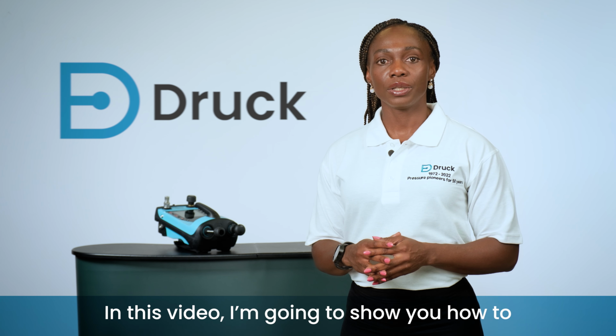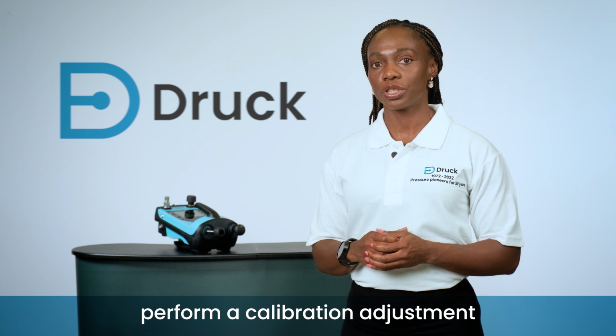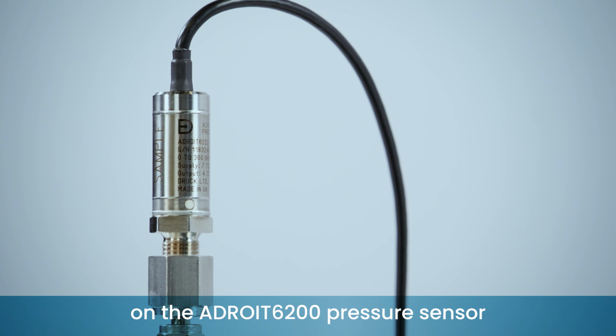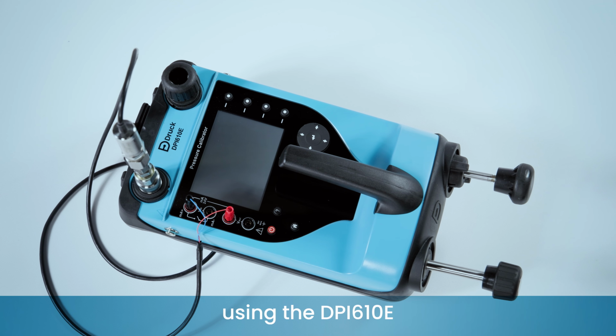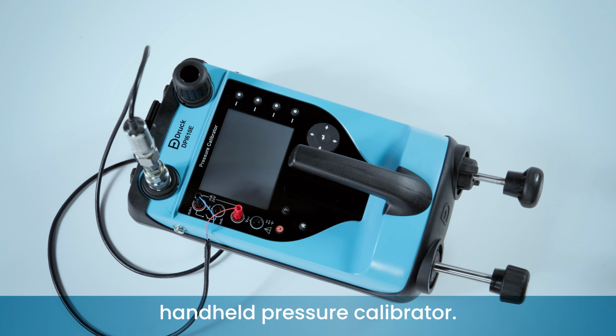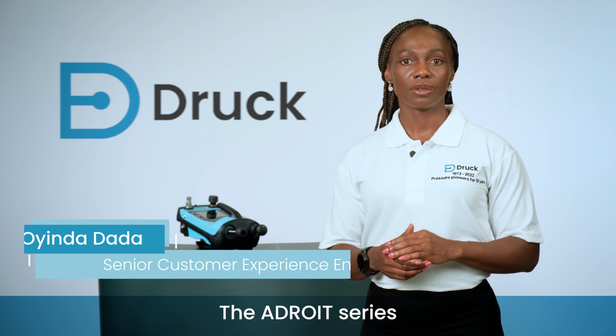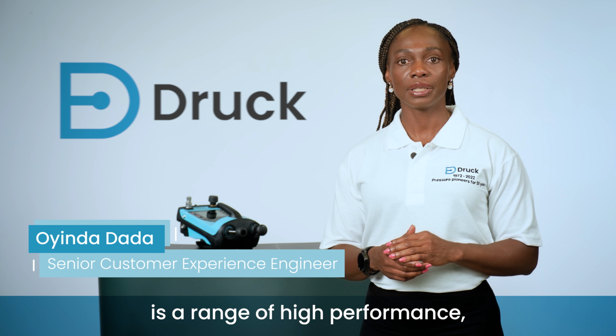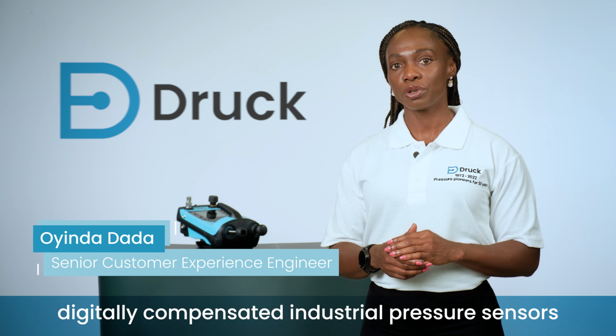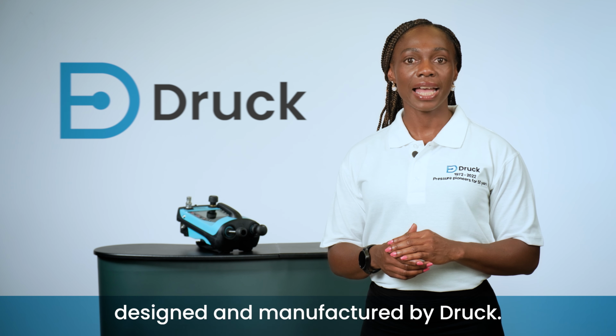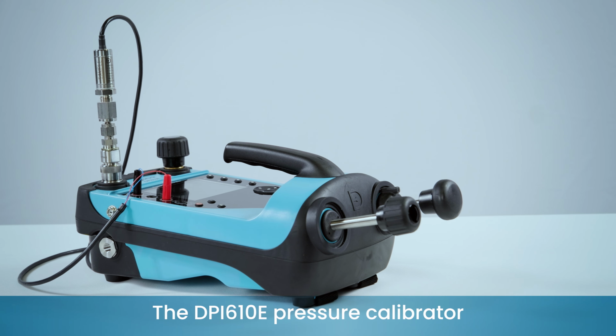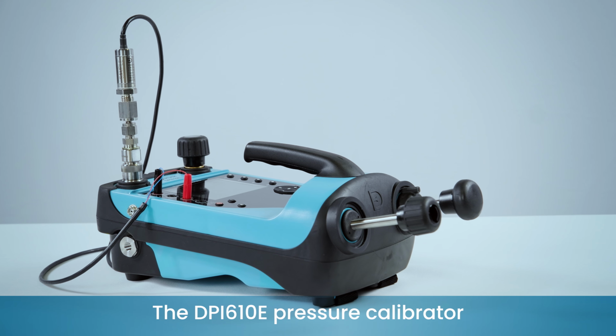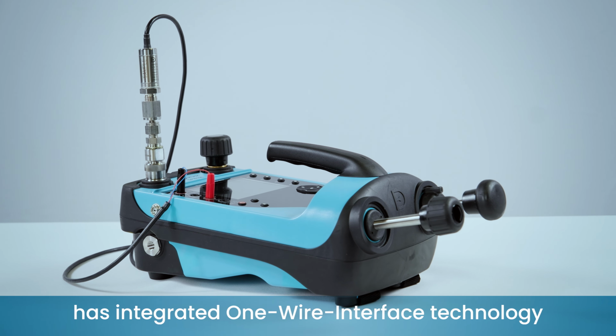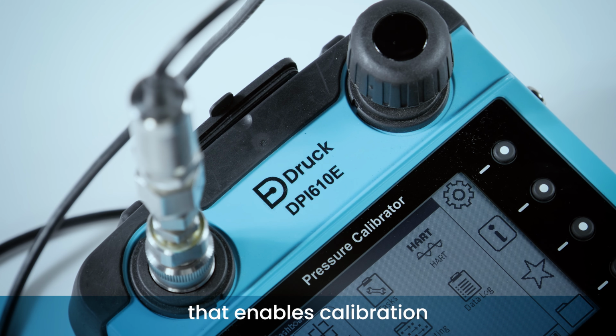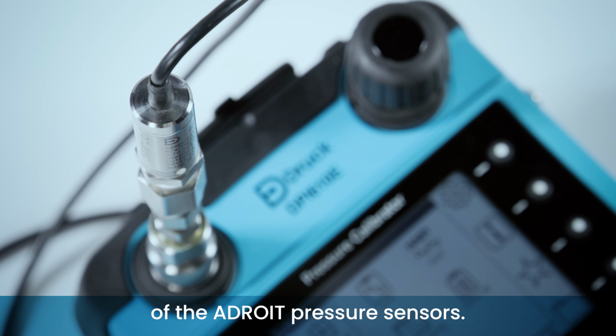In this video, I'm going to show you how to perform a calibration adjustment on the ADROIT 6200 pressure sensor using the DPI610E handheld pressure calibrator. The ADROIT series is a range of high-performance, digitally compensated industrial pressure sensors designed and manufactured by Druck. The DPI610E pressure calibrator has integrated one-wire interface technology that enables calibration of the ADROIT pressure sensors.